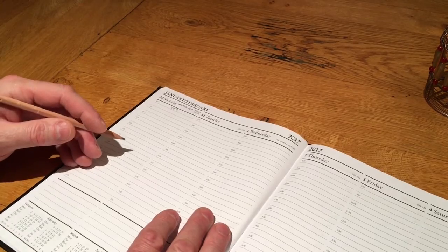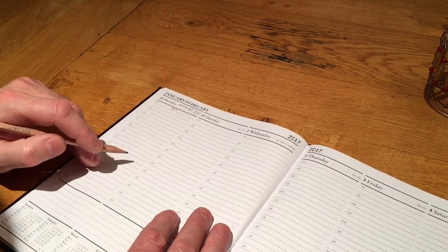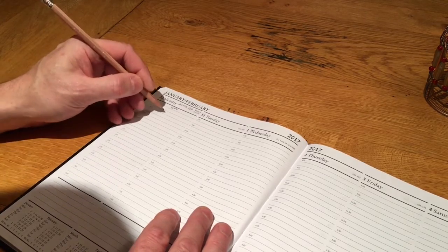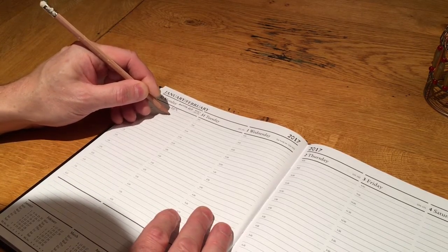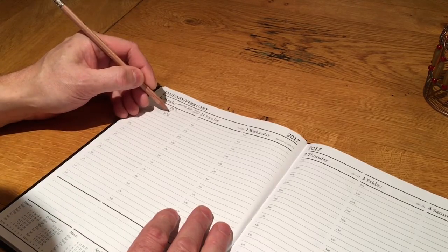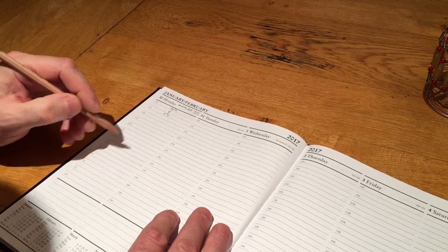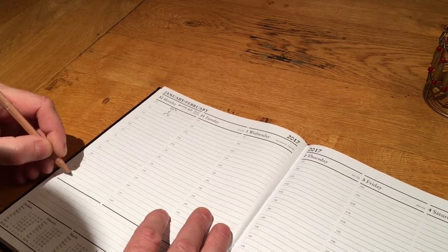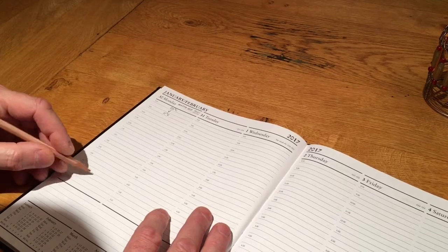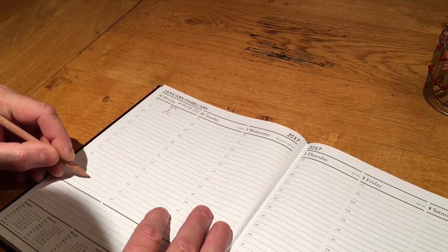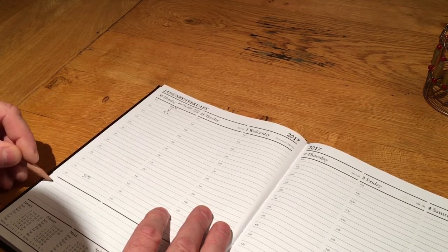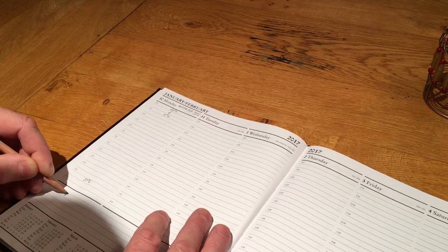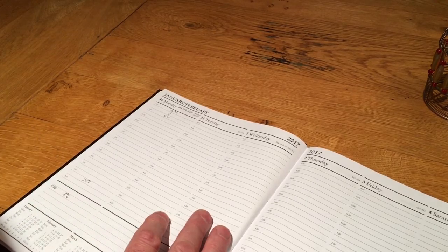I'm going to assume that I've got out of my bedroom by 9 o'clock in the morning, and there's no point in heating it to an occupational temperature thereafter, so I'm going to make it 11 degrees centigrade at 9 o'clock. Now, what time do I get back to my bedroom? Well, I might get back to my bedroom at 8 o'clock on Monday, so 8 o'clock on Monday, I'm going to warm it up again to 20 degrees centigrade, and then by 11 o'clock I would have gone to bed, and I'm going to set a temperature of 8 degrees centigrade overnight.